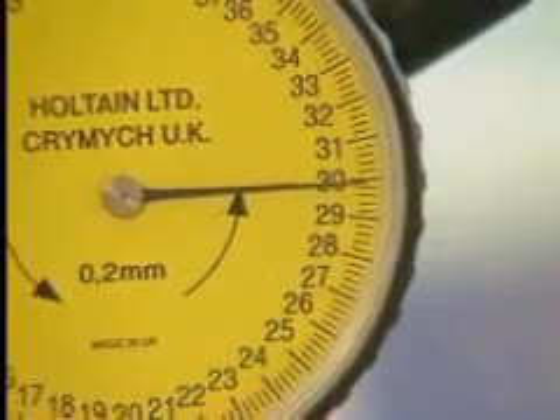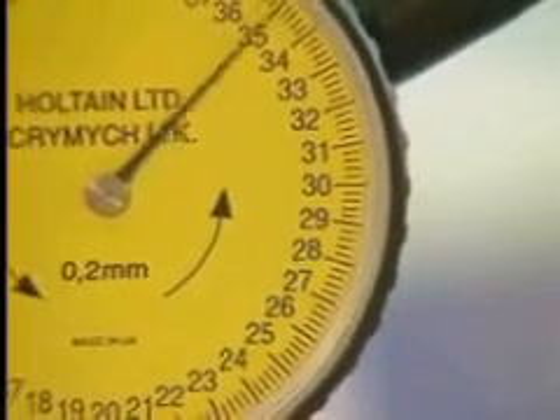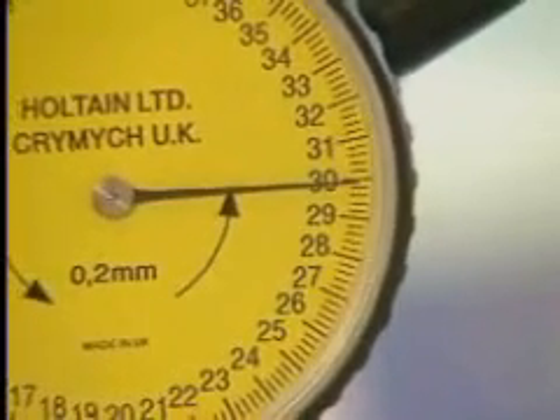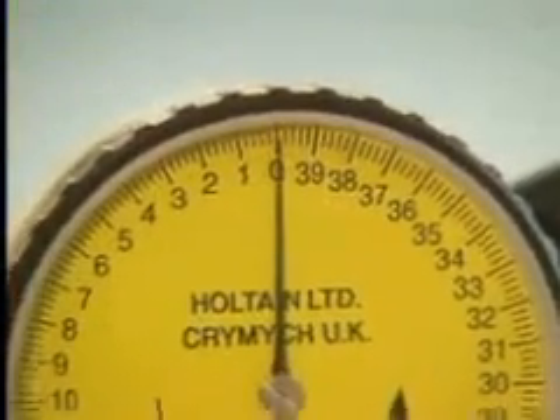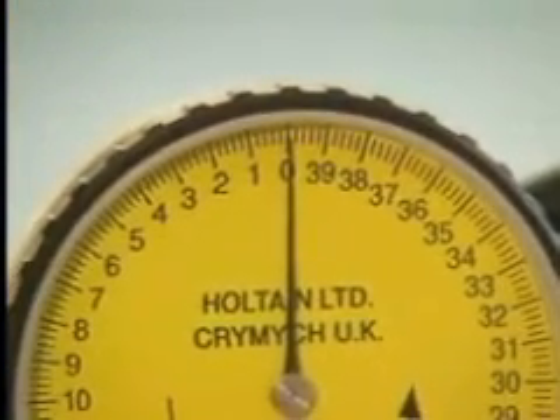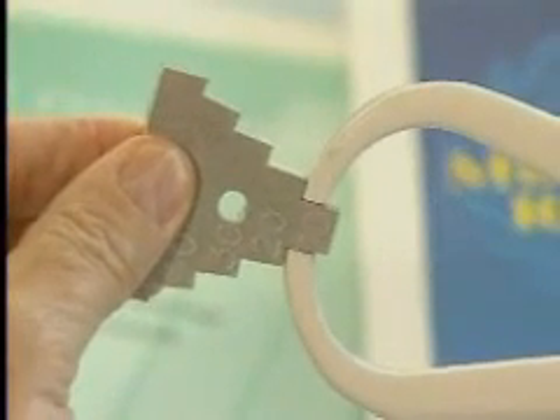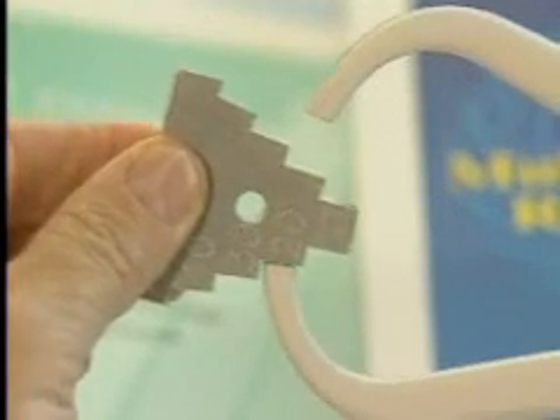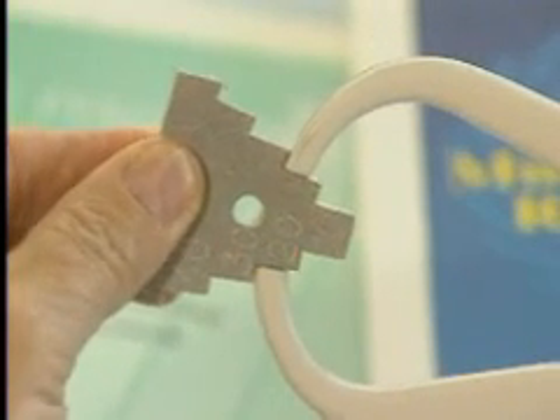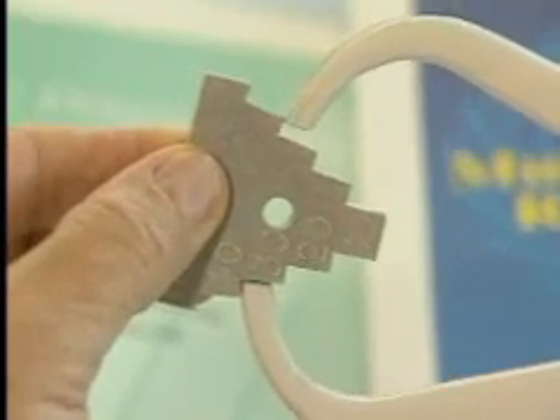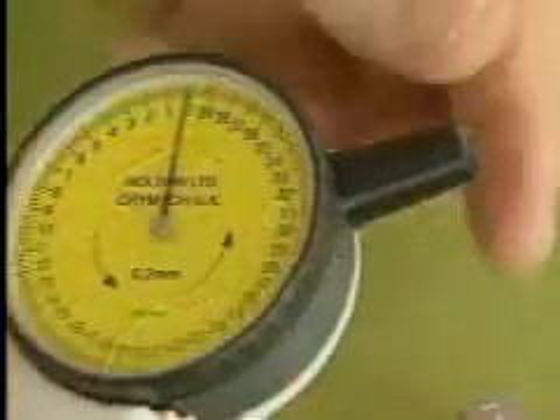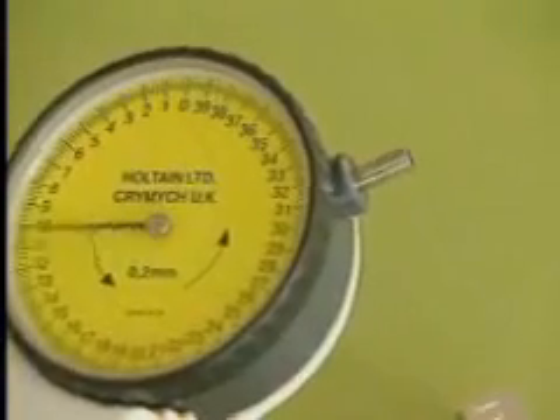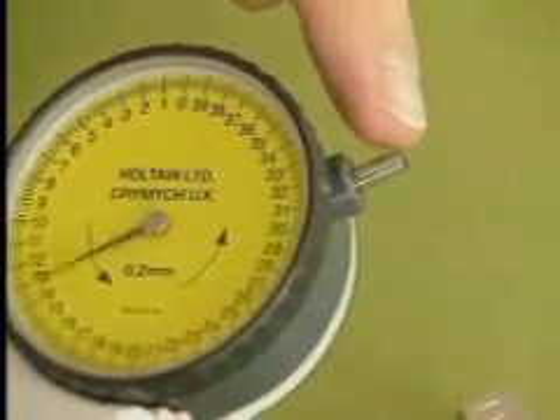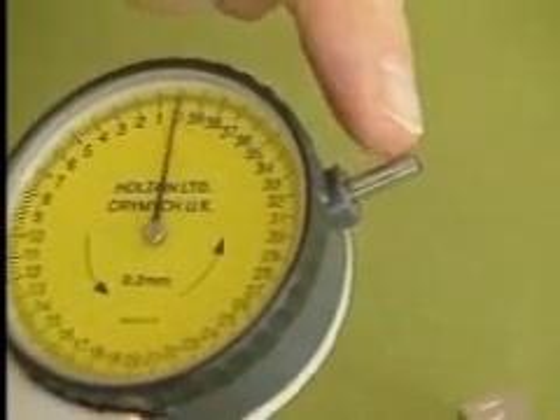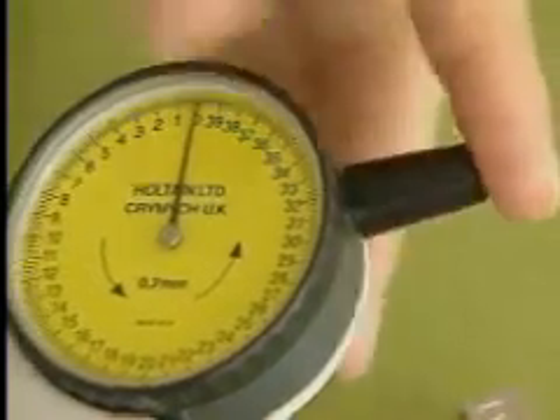When checking calibration status, there may be slight variations in readings at different test points, no more than 0.2 millimeters, caused by the metal block's contraction and expansion in response to fluctuations in temperature. If the caliper is off by 0.5 millimeters, it needs to be replaced. If the needle sticks or moves jerkily, there's a plunger in the center of the rotary dial that should be oiled lightly to help the needle move smoothly again.